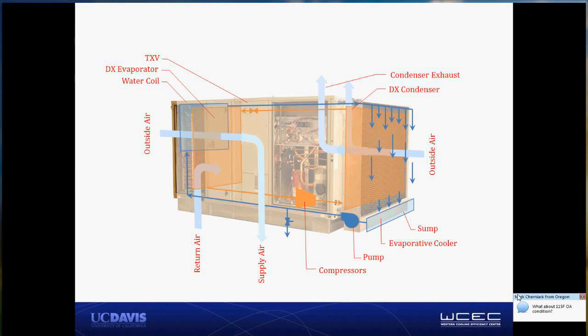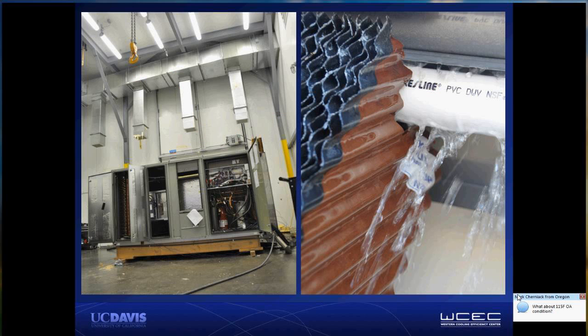And that sump water, which is cold, is circulated around to the other side of the unit and through a water-to-air heat exchanger placed in the ventilation air stream. So it cools down the ventilation air as it enters the unit and reduces load on the evaporator coil. That warmer water is brought back to the top of the direct evaporative media, and it's cooled as it passes across the media in contact with the condenser air.